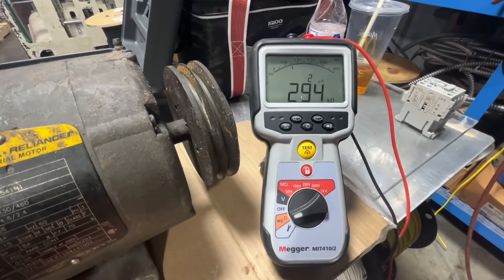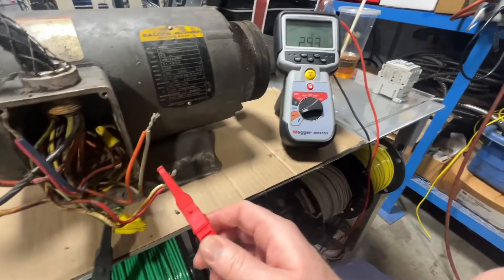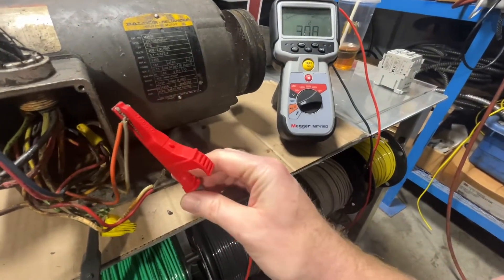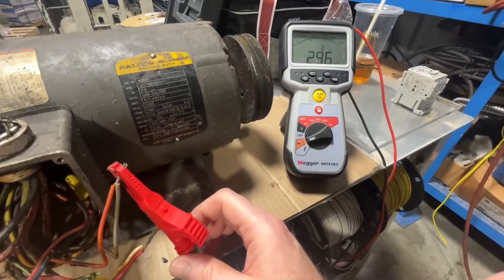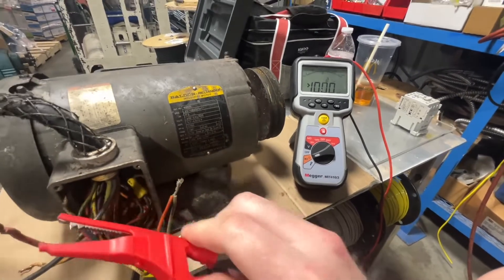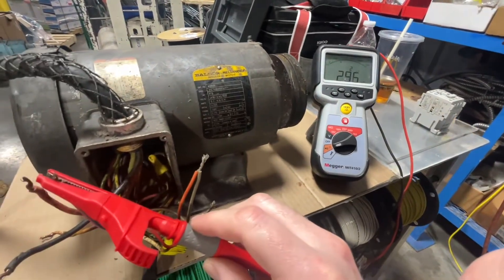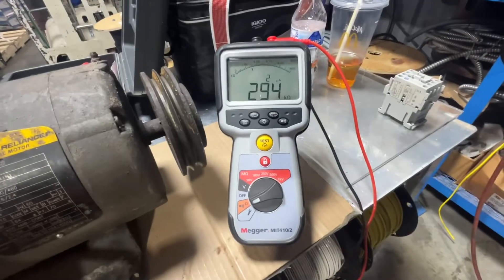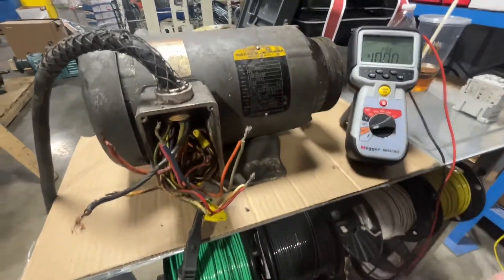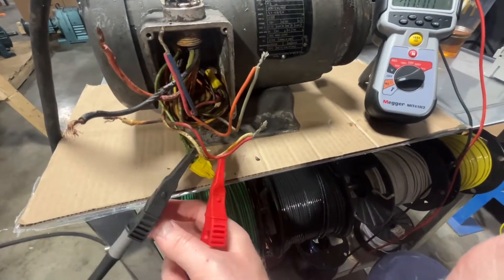As you can see, we're reading 294 megohms to ground on this first set. We'll go ahead and switch up to the next set — reading 295 megohms. They should all be about the same. The third set: 295, 294 megohms to ground. So this motor is reading a high resistance shorted to ground, from the motor frame to the windings.